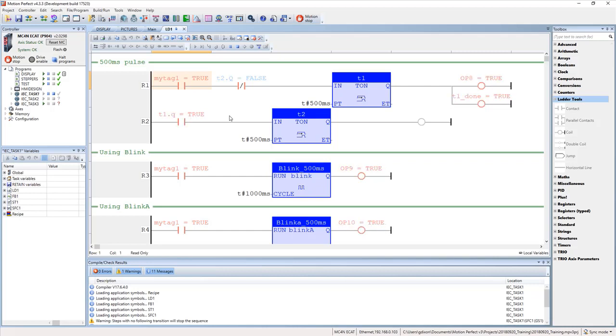The way ladder logic goes is it scans, then goes to the top, scans, goes to the top. With this blink, it just scanned once and then that process goes somewhere. It didn't really have to go through the process again. So that's why this is a pure 1 second clock. Well, this one, you have to go through that again. It's affected by the process, the program getting longer, affected by the scan time.